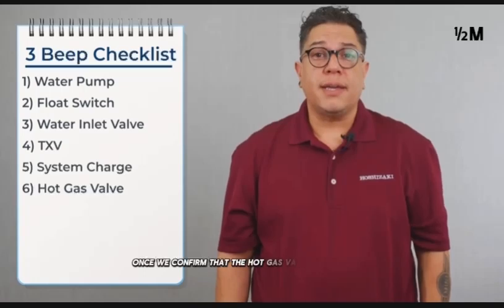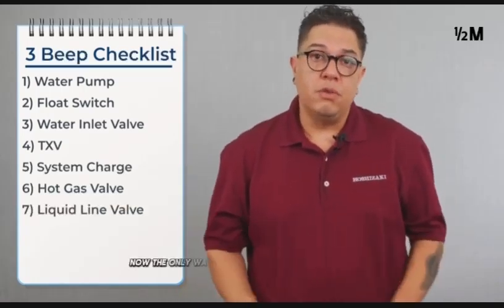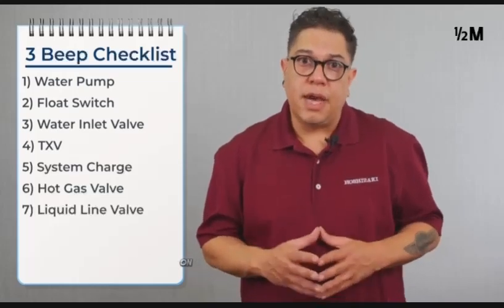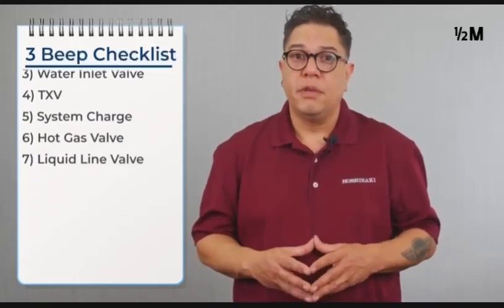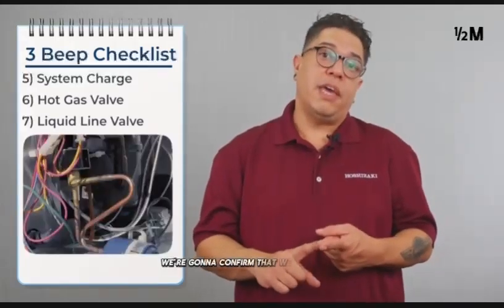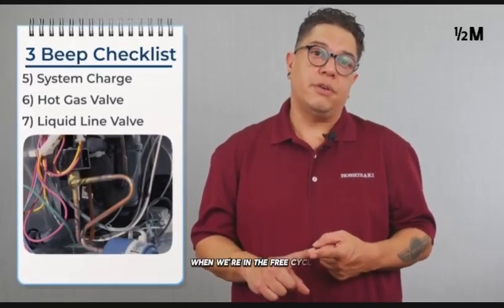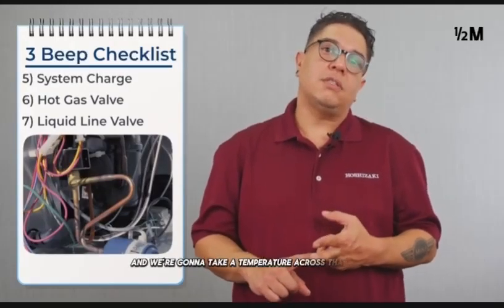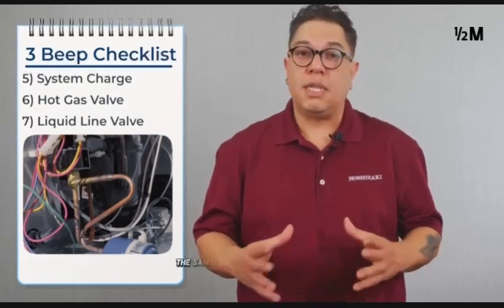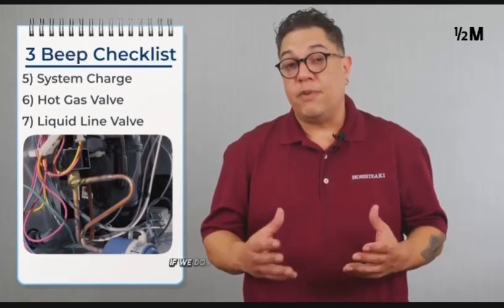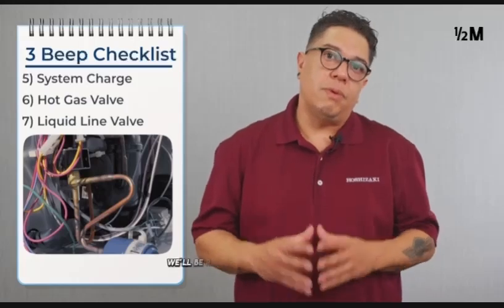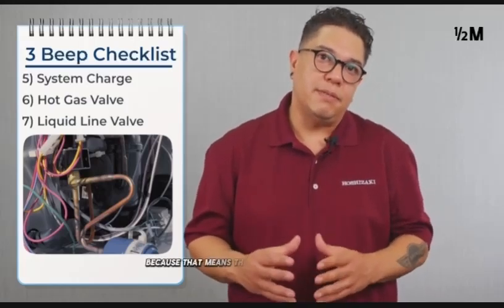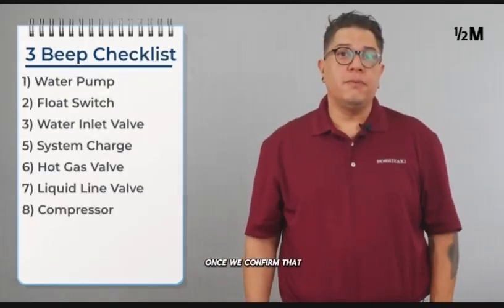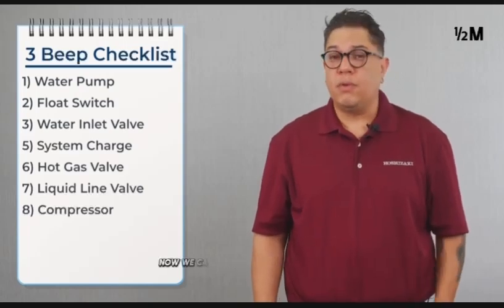Once we confirm that the hot gas valve is not leaking by, then we can move over to the liquid line valve. Now, the only way that the liquid line valve would fail on a 3 beep is if it wasn't opening or wasn't opening enough. What we're going to do is confirm that we have power when we're in the freeze cycle, and we're going to take a temperature across that valve. What we should see is the same temperature on both sides. If we don't and we have a differential, we'll be replacing the liquid line valve because that means that it's partially restricted.